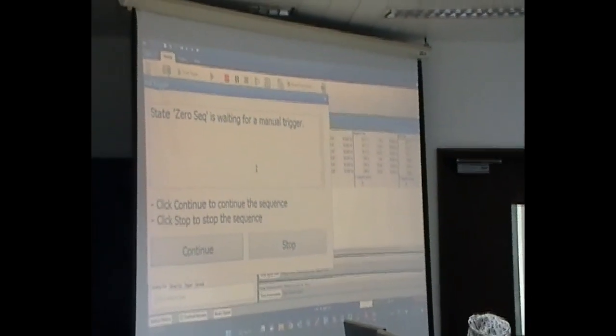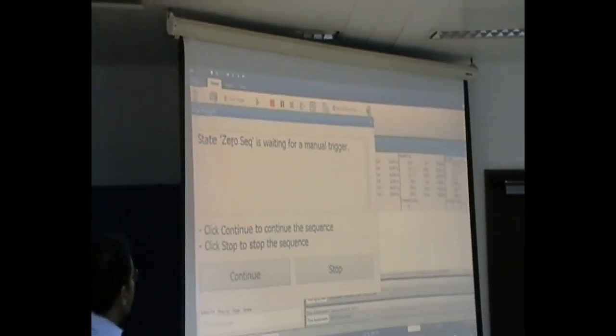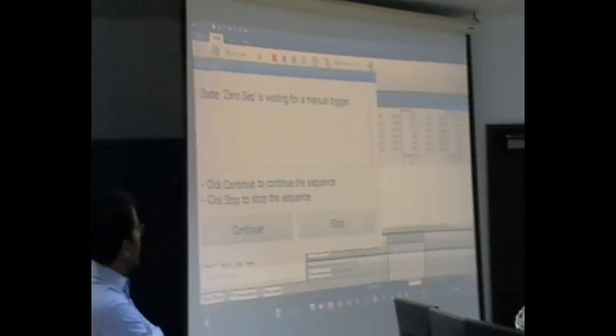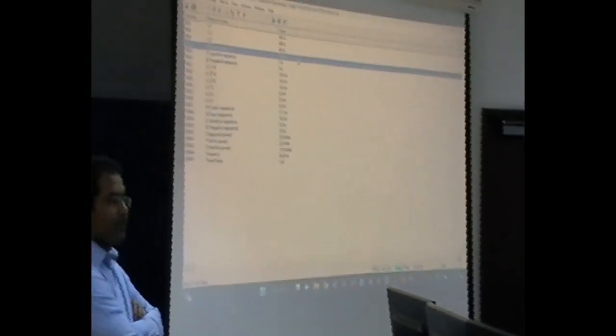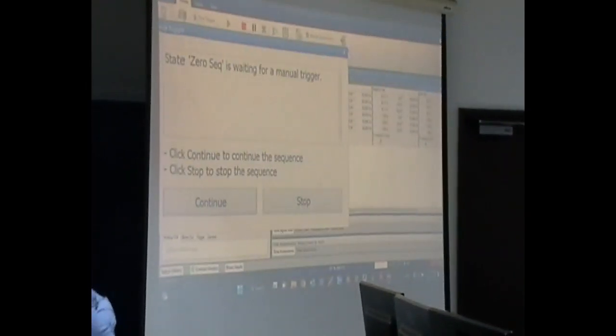We'll go to the last one in the measurement, which is zero sequence. We are injecting the same values again but with the same angle, basically zero angle. So what we are expecting in the zero sequence is the summation of all phases. Now we can see it in the testing here.